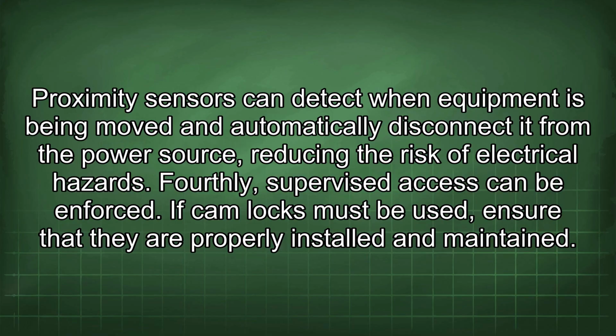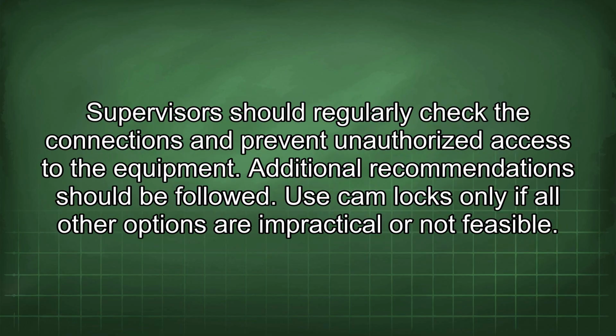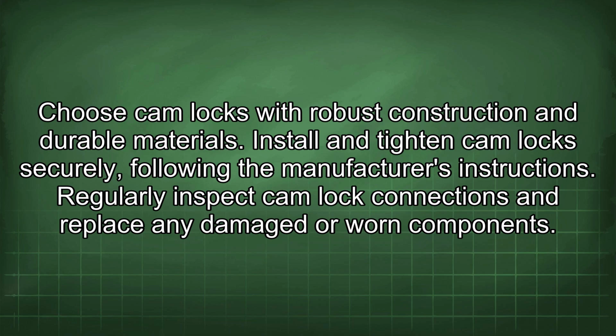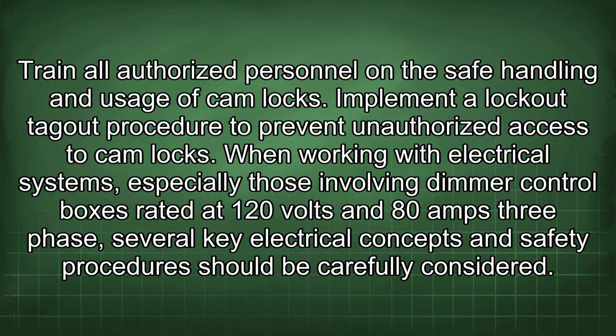If cam locks must be used, ensure that they are properly installed and maintained. Supervisors should regularly check the connections and prevent unauthorized access to the equipment. Additional recommendations should be followed. Use cam locks only if all other options are impractical or not feasible. Choose cam locks with robust construction and durable materials. Install and tighten cam locks securely, following the manufacturer's instructions. Regularly inspect cam lock connections and replace any damaged or worn components. Train all authorized personnel on the safe handling and usage of cam locks. Implement a lockout-tagout procedure to prevent unauthorized access to cam locks.